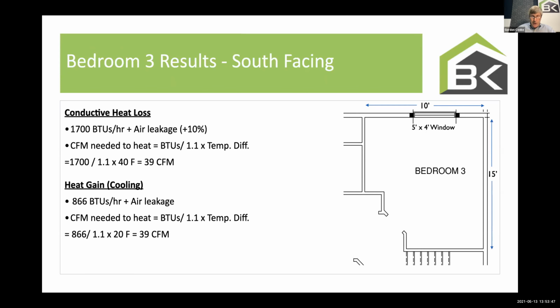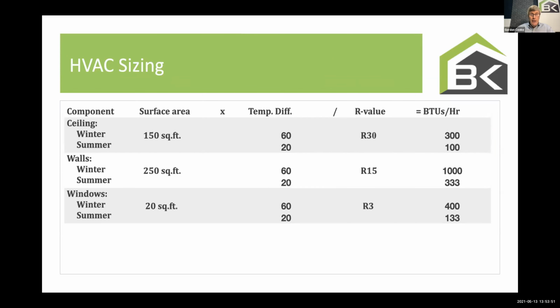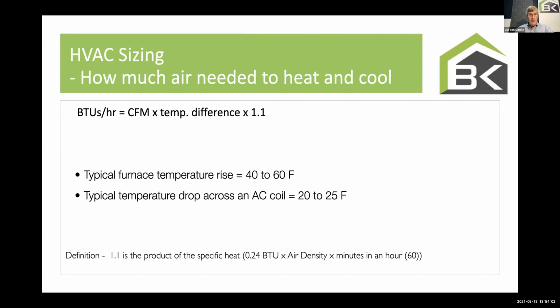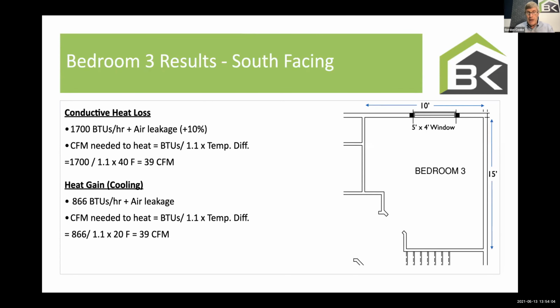If I told you, oh, I thought I had it, the total heat gain of that room, I'll just go back quickly. So the total heat gain of that room, heat loss, the 300 plus the 1,000 plus the 400, that's 1,700 BTUs. Everybody okay with that? 1,700 BTUs out of that bedroom 3.